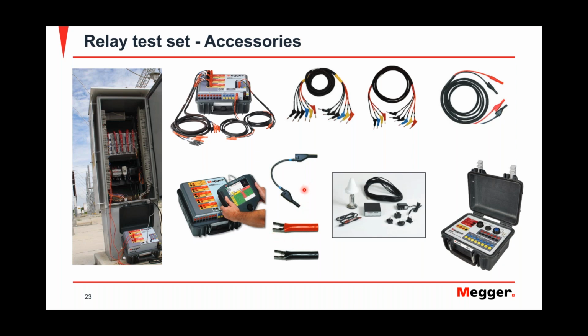Having some lugs, some jumpers. This is an example of if you're doing end-to-end testing and you need a GPS to synchronize the test sets. This is the GPS and the receiver. This is an example of, let's say you're testing a recloser and you need an interface that goes from the relay test set to the recloser controller. You've got to know, hey, I'm testing a recloser, know the capabilities and what's needed for the test set to do that test.